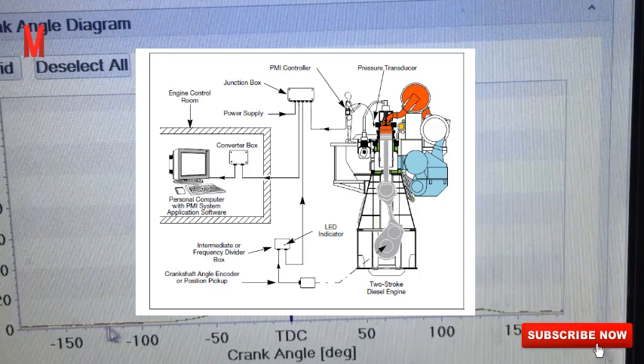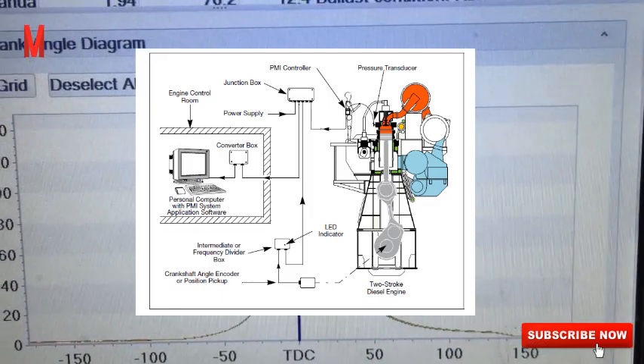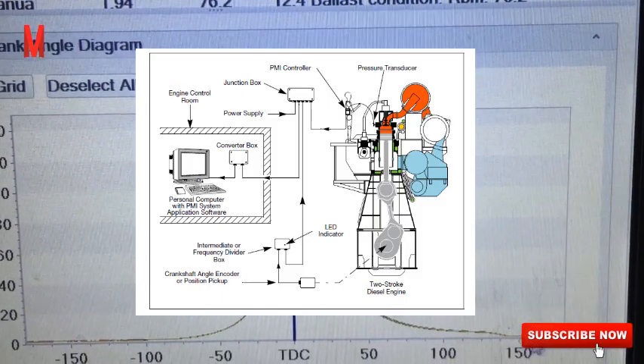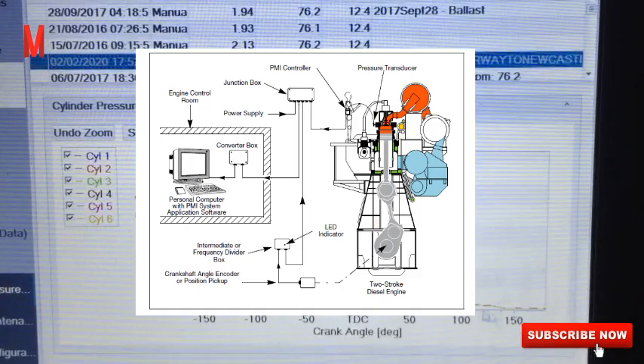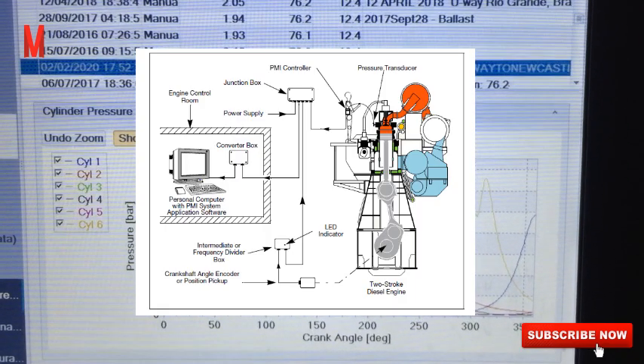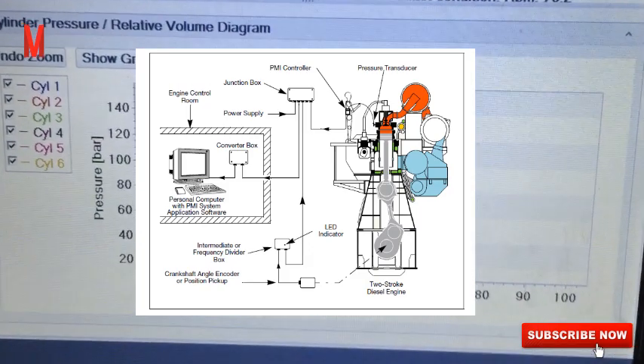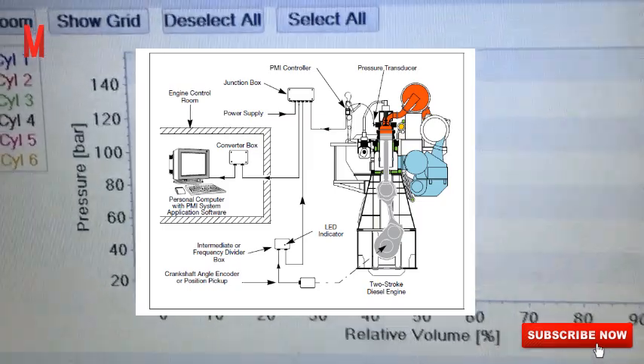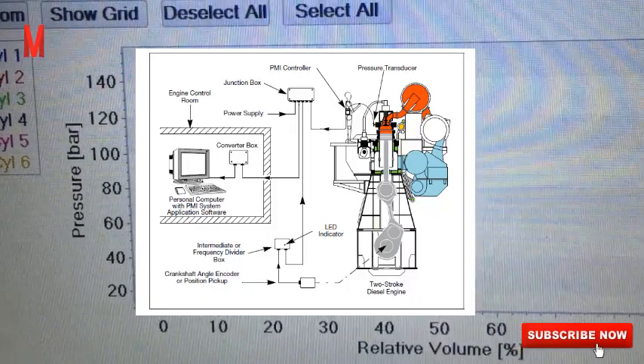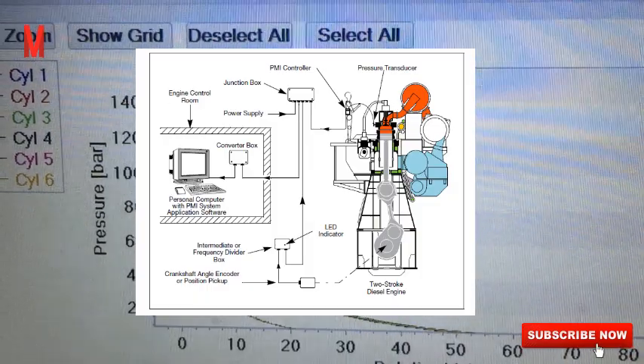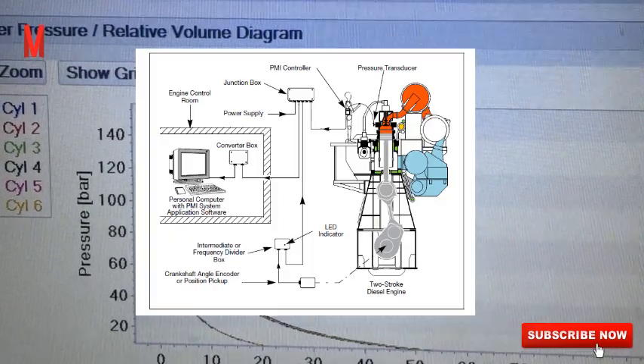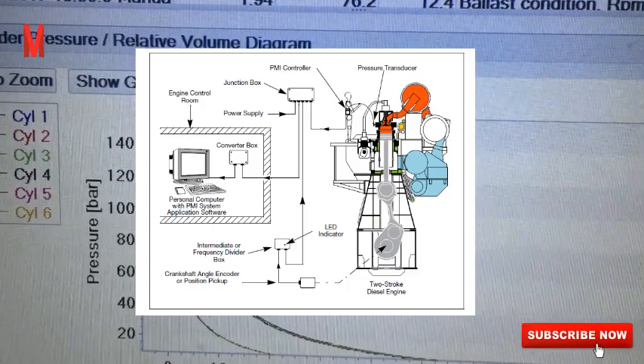Gone are the days when engineers used the indicator cards. What is new today is the engineer, when measuring the cylinder pressure, can install or mount the piezoelectric transducer or the pressure transducer into the indicator cock of each cylinder to be measured. The transducer is manually moved from one cylinder to another between each set of measurements.